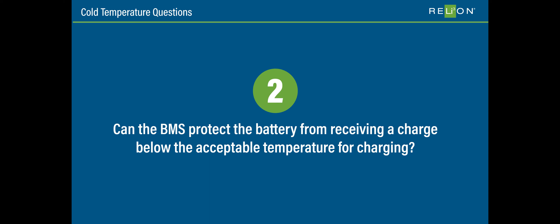Can the BMS protect the battery from receiving a charge below the acceptable temperature for charging? No. Our standard analog BMS, which is in most of our plastic case products, does not have protection for cold temperature charging. You've got to monitor that on your own manually. We do have a few products with a digital BMS, in the steel case and usually 48 volts, and you can email us if that's the product line you're working with. But for most cases, no.